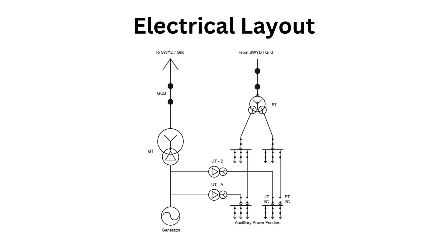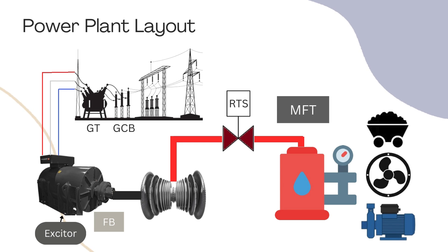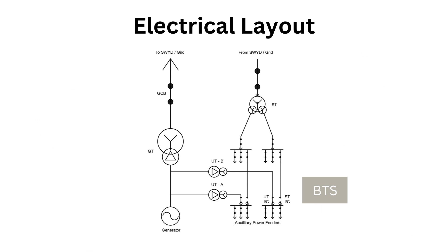Each element of the power plant requires an on/off button for control. The GCB controls the connection between the grid and the generator, and the field breaker controls the excitation system. The RTS cuts off the steam flow to the turbine, and the Master Fuel Trip (MFT) cuts off the fuel flow and extinguishes the flame in the boiler. The Bus Transfer Scheme (BTS) is used for UT/ST changeover to select the power source — either the Station Transformer or Unit Transformer.